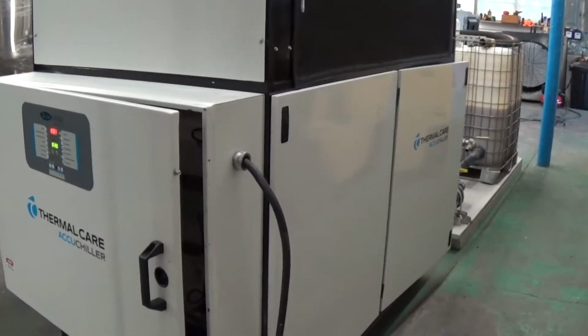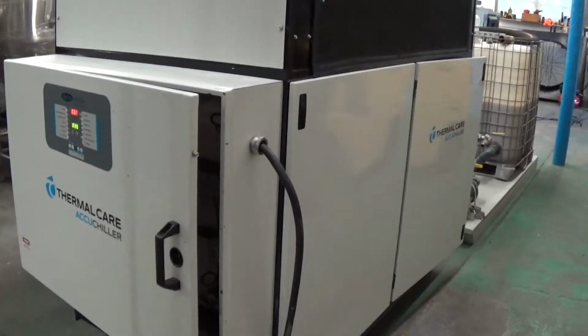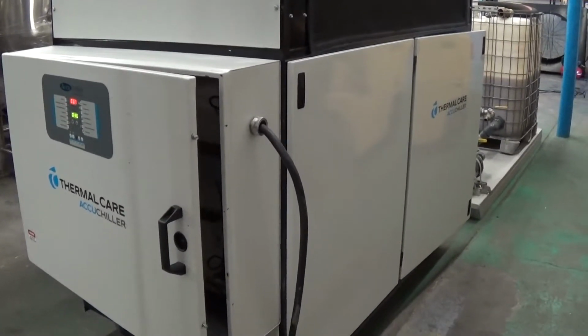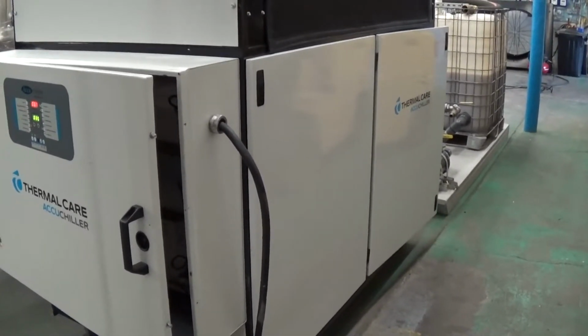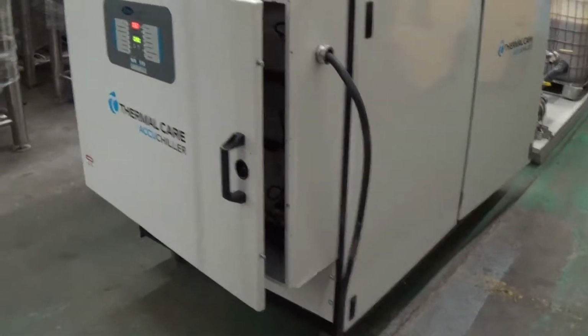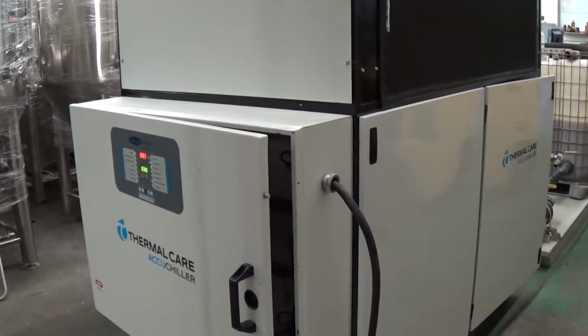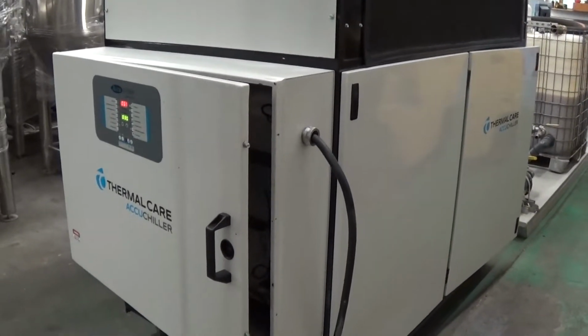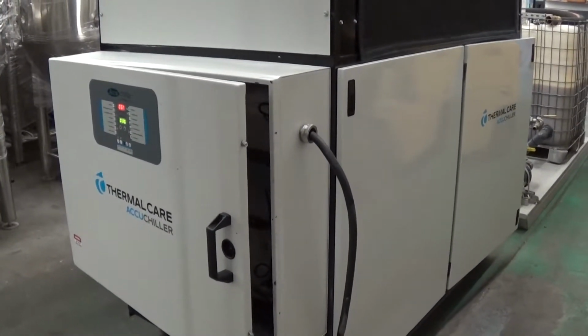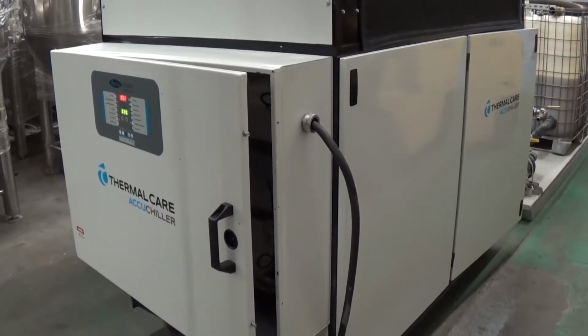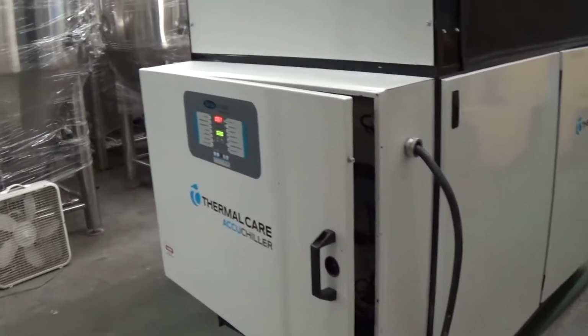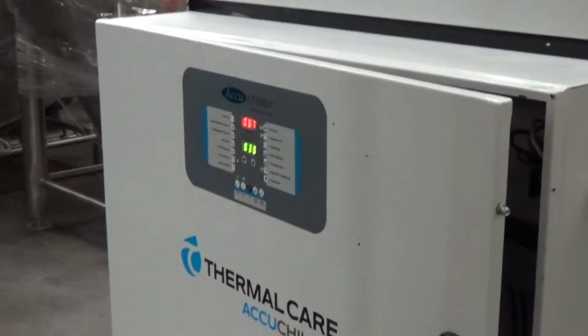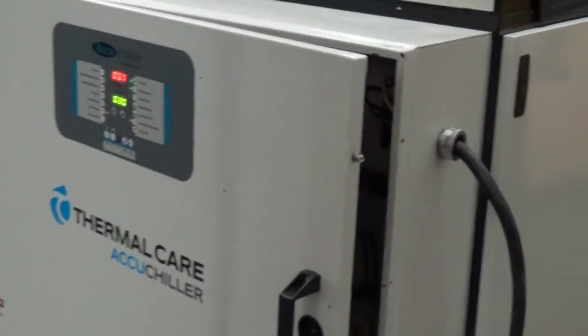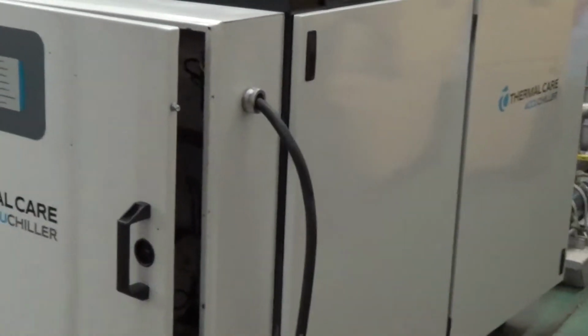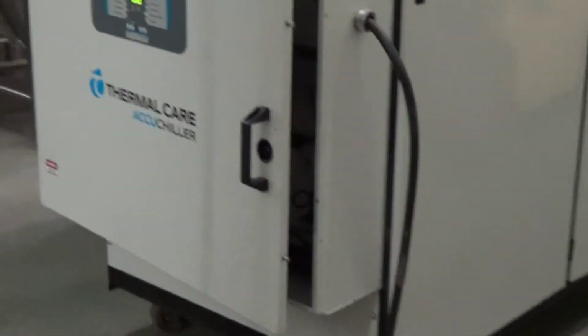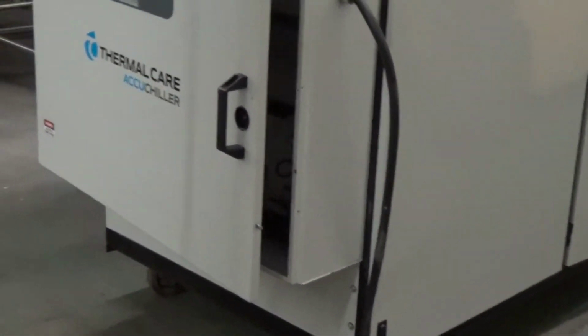If and when you do need to chill at that temperature, if the chiller never shuts off because of the hot gas, you can disconnect the hot gas option. Some folks like to keep the hot gas going the whole time, just to stabilize a tighter temperature set point. Up at the higher set point ranges, it will go past the set point and then turn everything off. Give us a call if there's any misunderstanding of what the hot gas bypass option is. It is an upgrade. It is a feature on chillers this size.